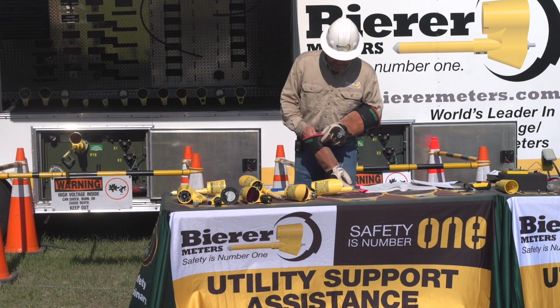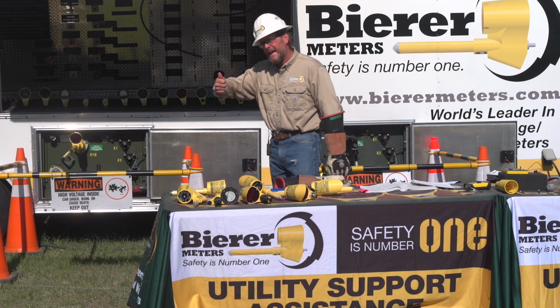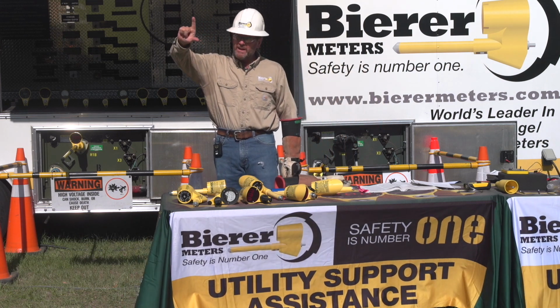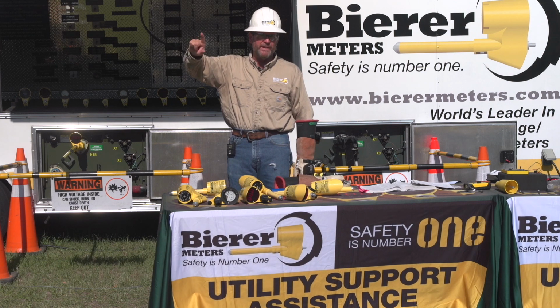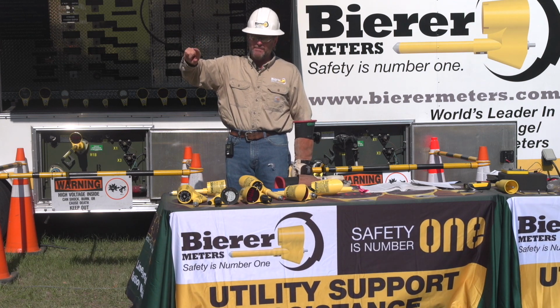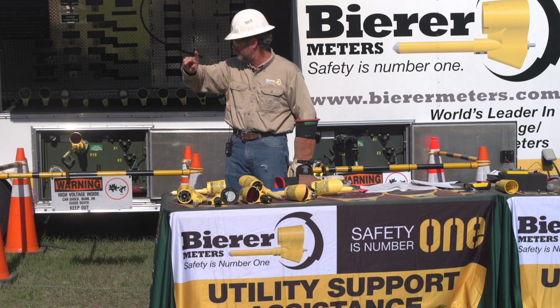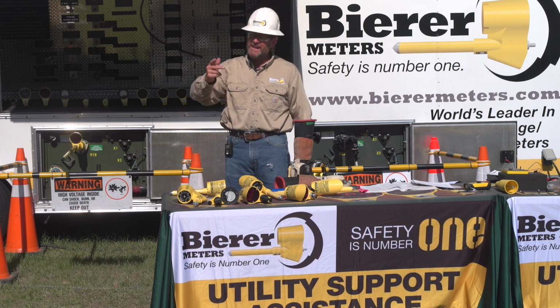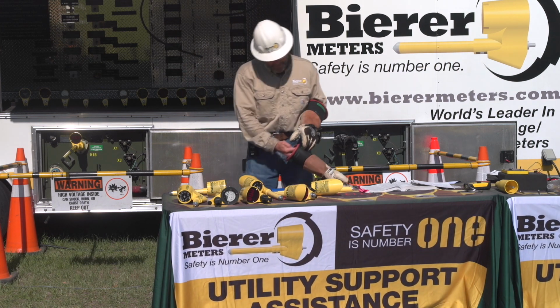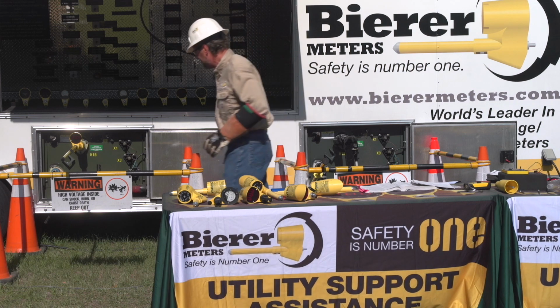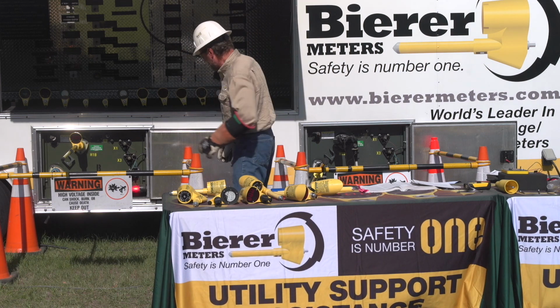The second thing is, so we test, and then we're going to open. We're going to complete and confirm a visual open air gap. Lockout, tag out, we're going to have that in place. Next thing we're going to do is take our meter and test. So let's do that, we got a confirmed open air gap.